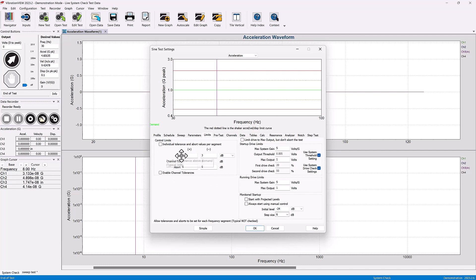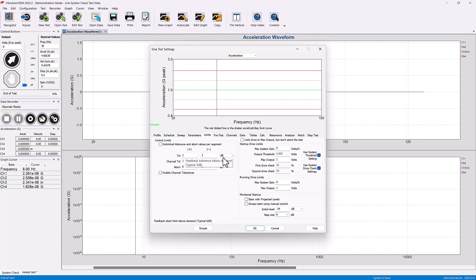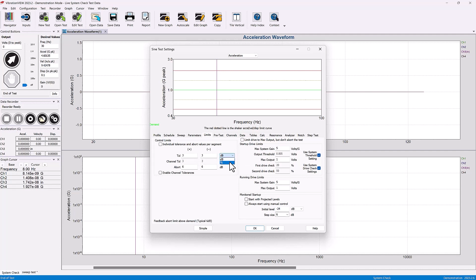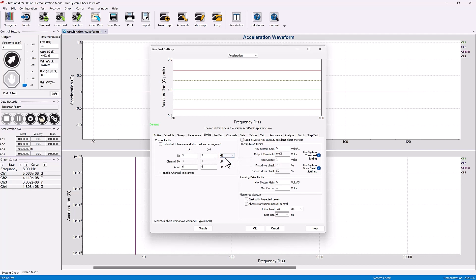The tolerance plus and minus limits are the points at which the controller is going to switch from startup mode to run mode. Generally this is set at plus or minus 3dB level. We have opportunity to change it to a particular percentage of the control, but this is where the controller is going to switch from startup mode to run mode.